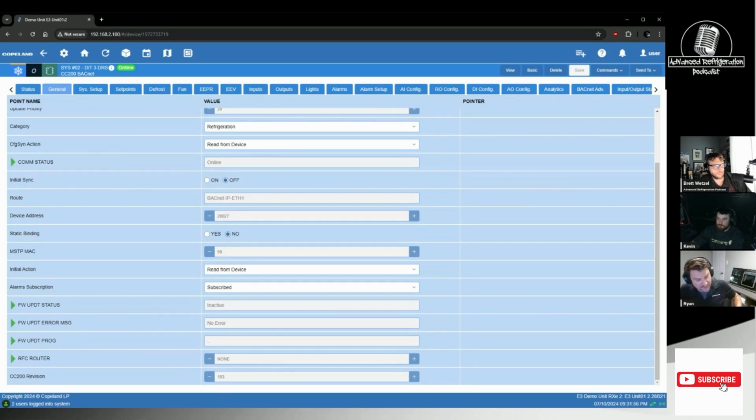Configuration's not too bad. I don't find, mind you, I've been playing around with them a bit. So the easiest way I find is on the display. There's a little Bluetooth display where the temperature is read out. By default, the Bluetooth is off. If you want to turn on the Bluetooth, hold your finger at the top right. You're going to see set flashing on the bottom left, and it's going to give some beeps at you. It sounds like an old Nintendo game whenever it starts beeping. Whenever the set is solid on, you can swipe to the right. You're going to see a Bluetooth icon. Hold the Bluetooth icon, same idea. You're going to hear it beep, and then Bluetooth is going to be on.